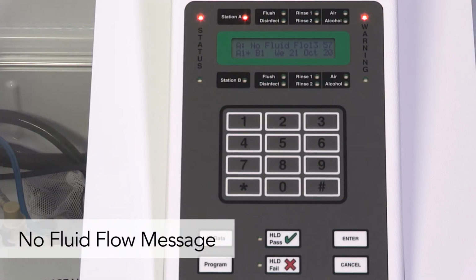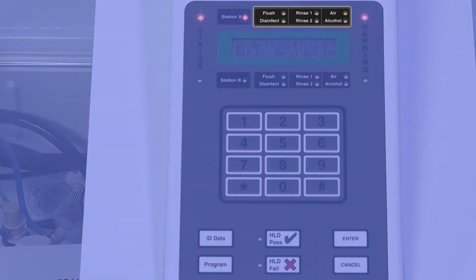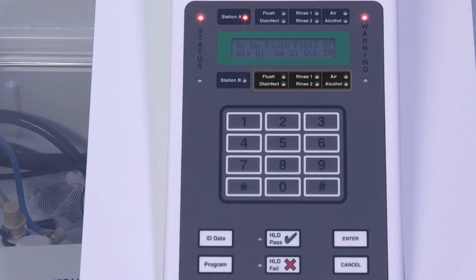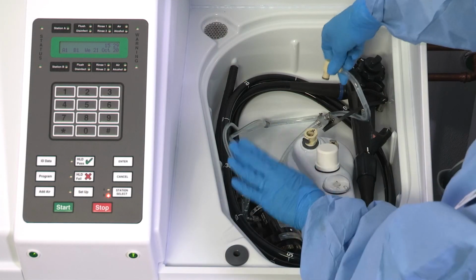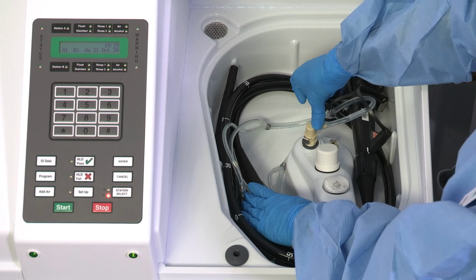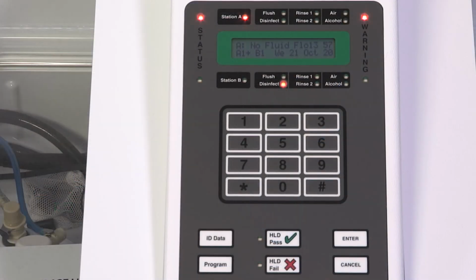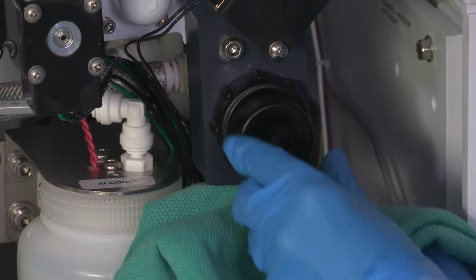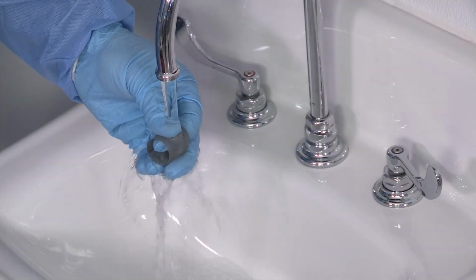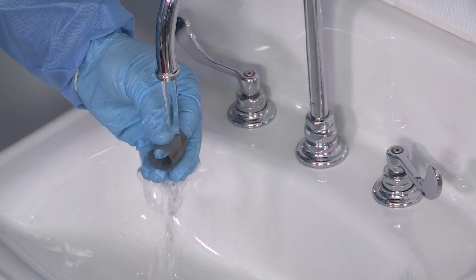A no fluid flow error message occurs if no fluid flow is detected. Troubleshoot by checking the cycle indicator lights. If the unit is in the rinse stage, make sure the hookup connector is snapped securely into the basin port on the machine. If in the disinfection phase, cancel the cycle. Once the basin has reset, check the disinfectant filter to make sure it is clean.